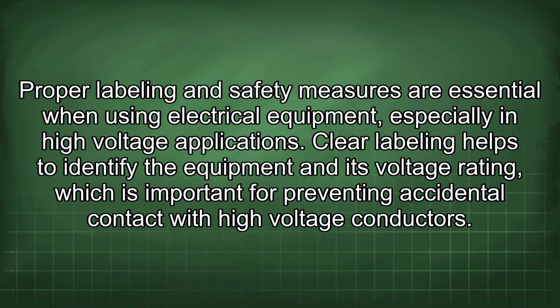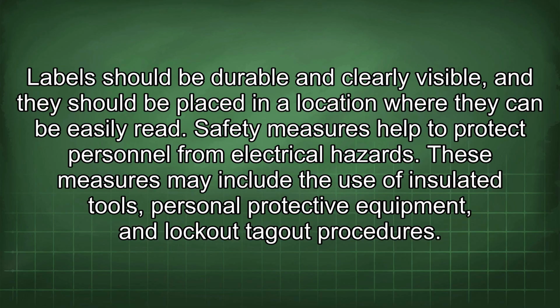Proper labeling and safety measures are essential when using electrical equipment, especially in high voltage applications. Clear labeling helps to identify the equipment and its voltage rating, which is important for preventing accidental contact with high voltage conductors. Labels should be durable and clearly visible, and they should be placed in a location where they can be easily read. Safety measures help to protect personnel from electrical hazards. These measures may include the use of insulated tools, personal protective equipment, and lockout-tagout procedures.